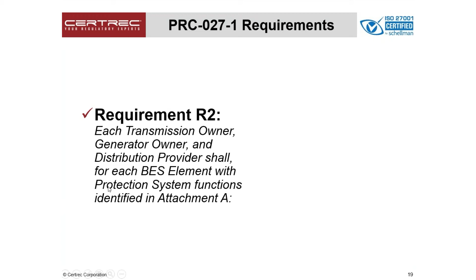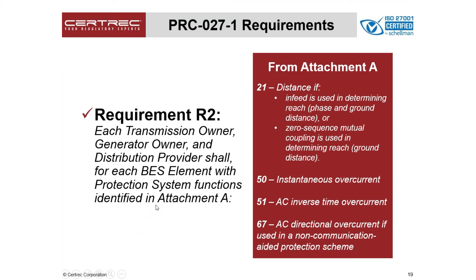And going into requirement 2. Again, this is straight out of the standard, but basically you're looking at any kind of protection element that can affect the bulk power system. And out of attachment A, we talk about the distance relays, which are number 21, the instantaneous overcurrent, the time overcurrent relays, and then also directional overcurrent relays if used in a non-communication aided protection scheme. So these are the main ones they're looking at for coordination between typically the generator and a transmission owner.